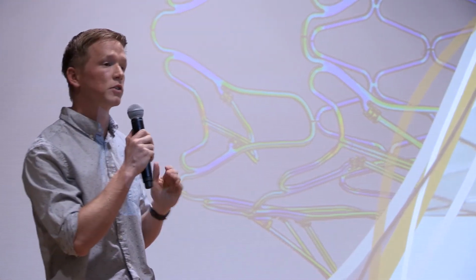This stent design has since then been turned into a metallic prototype that was laser cut from stainless steel tubing and is in the process of undergoing testing both to validate our simulation model and to create benchmark values that will enable us to compare to other currently available stents.